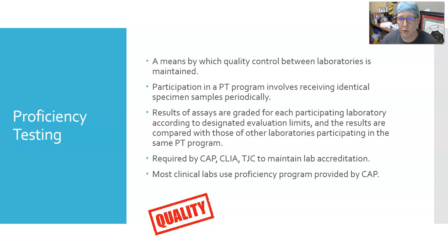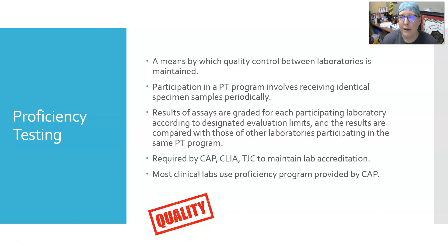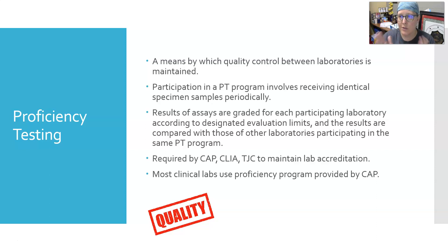Proficiency testing is a means by which quality control between laboratories is maintained. Participation in a proficiency testing program involves receiving identical specimen samples periodically. The agency, usually CAP, sends specimens out to multiple labs and the results are sent back to CAP. They grade everybody based on their performance — the results of the assays are graded for each participating lab according to designated evaluation limits and compared with those of other laboratories in the same PT program. That allows you to see not only if you can get the results right on an unknown, but also how you're faring compared to other laboratories.